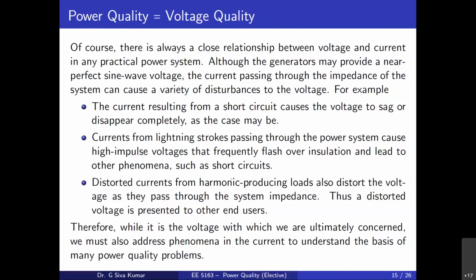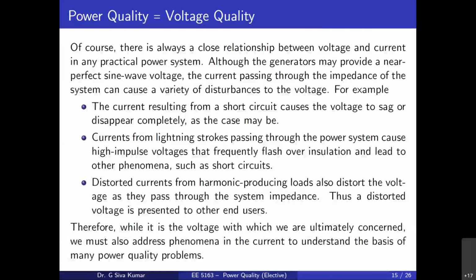This also creates a voltage sag, even an impulse voltage, at this point. The other point is distorted current from harmonic producing loads. Distorted currents due to harmonic producing, nonlinear loads also distort the voltage as they pass through the system impedance. Thus, a distorted voltage is presented to other end users. Distorted currents also distort the voltage.